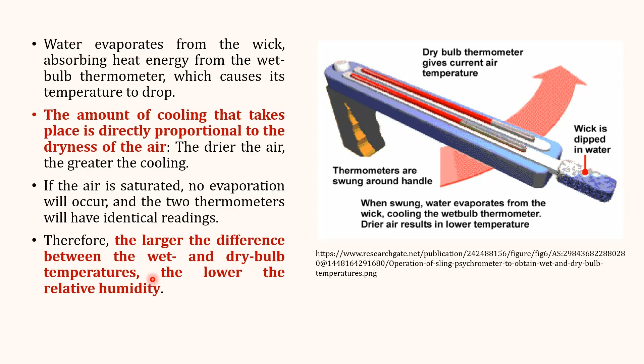In a sling psychrometer, these thermometers are swung like this around the handle, and in this process water evaporates from the wick, which cools the wet bulb thermometer. The amount of cooling that takes place is directly proportional to the dryness of the air, because if the air is already saturated, no evaporation will occur, and both thermometers will have identical readings. But if the air is dry, meaning it has less water vapor, more evaporation will occur and greater will be the cooling. Therefore, the larger the difference between the wet and dry bulb temperature, the lower the relative humidity.